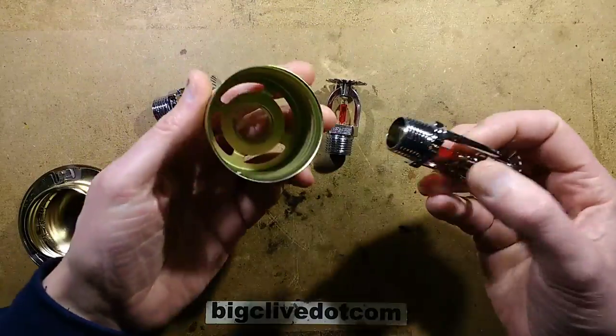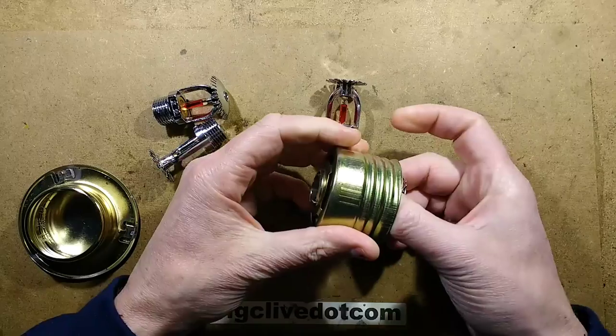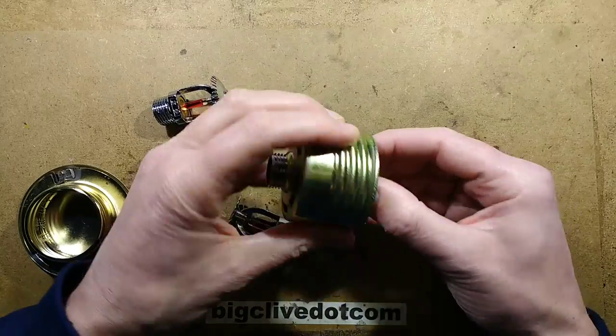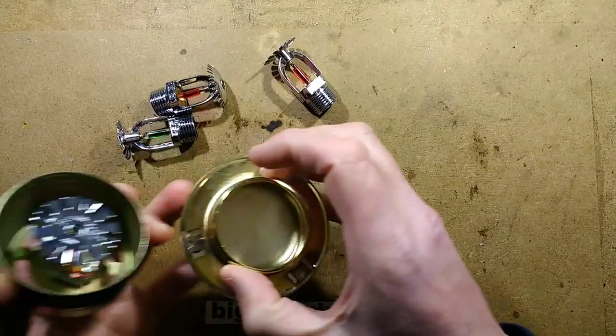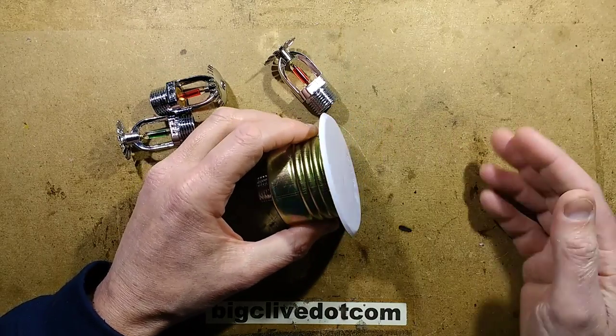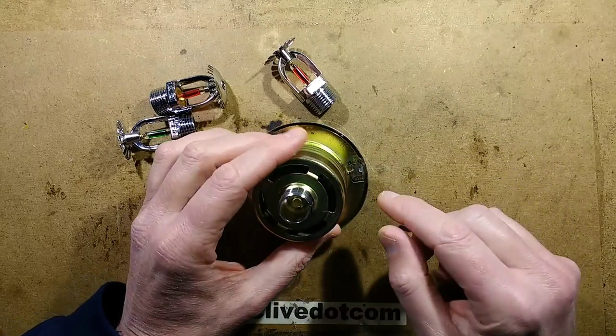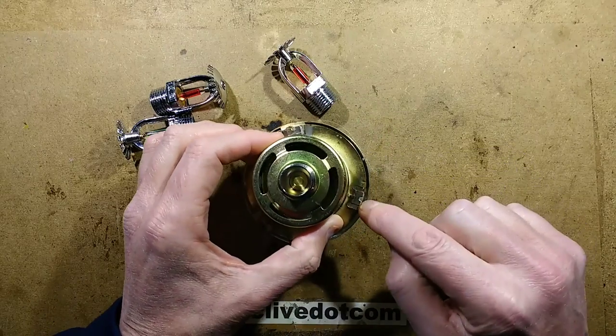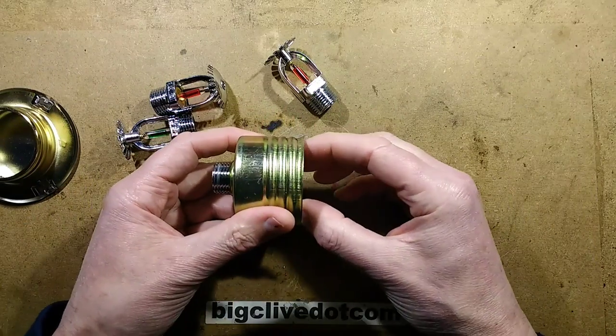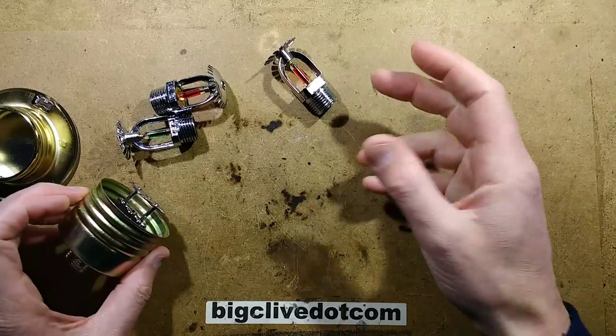One of the interesting ones here was a sprinkler with a drop-down mechanism. It goes into this cup, and once it's screwed in, a cover goes in the front, meaning it's completely hidden. I thought: is this just cosmetic? But if you have this flushed to a ceiling, it means someone is less likely to hit it with a scaffold or pole while working up there, so it does protect it. When heat from a fire reaches it, there must be an alloy that just melts and the cover drops off. That reveals the sprinkler, and the deflector then pops down to allow water to divert out. The heat can also travel up and make the capsule inside fail, and that is what triggers it.